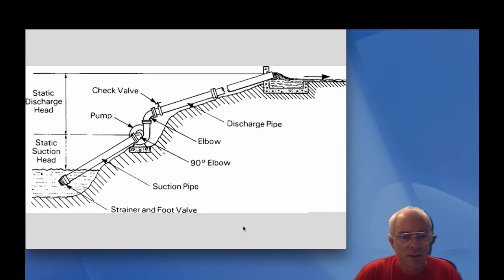Let's look at our pumping situation again. Now let's say we're not just dumping water out, we're pumping into a sprinkler system and the sprinkler system requires 65 pounds of pressure, 65 psi. Now we have to convert that into vertical head to add to our total dynamic head, then go back to the pump curve and see what pump is required.